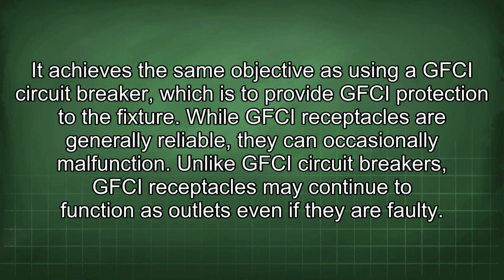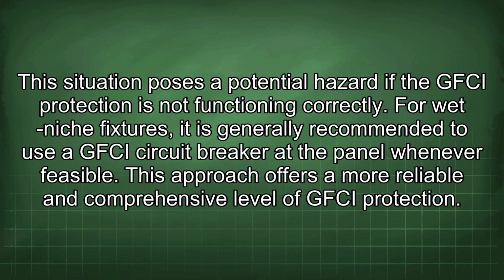fixture. While GFCI receptacles are generally reliable, they can occasionally malfunction. Unlike GFCI circuit breakers, GFCI receptacles may continue to function as outlets even if they are faulty. This situation poses a potential hazard if the GFCI protection is not functioning correctly. For wet niche fixtures, it is generally recommended to use a GFCI circuit breaker at the panel whenever feasible. This approach offers a more reliable and comprehensive level of GFCI protection.